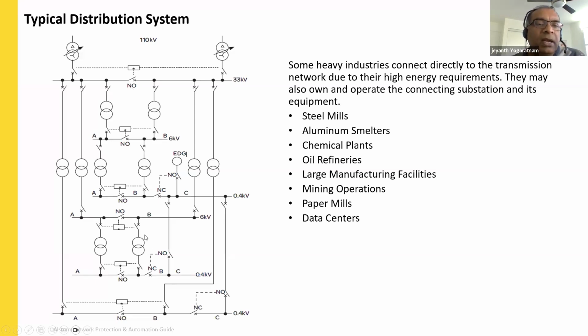And each and every feeder down the line, in this particular application, has a 6 kV voltage bus and a 0.4 kV voltage bus, which is a 400 volt system. So each and every bus is fed with two feeders, with the tiebreaker left open. This will improve the reliability of the supply in the event of failure of one feeder.